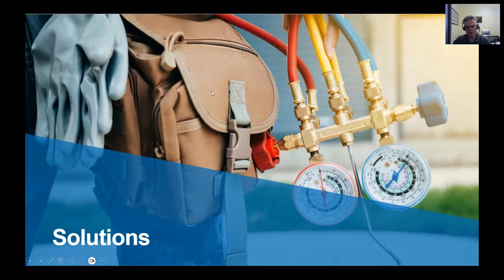So we look at residential, commercial AC and heat pumps - this is ducted splits, rooftop units, light commercial, mini splits. You can see there really isn't any refrigerant that falls into the non-flammable category here, but they're transitioning mainly to 454B and R32 in this sector.